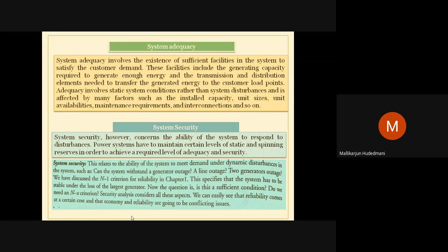That ensures the state of health of the system for upcoming contingent changes. So that kind of measure, Nx criterion based measures, need to be taken as a loop, always keeping alert. If this component fails, or certain components together fail, what is the impact of that failure due to internal failure, external failure, or its own aging effect, whatever it is, the remaining system left is in danger. Is it secured? Is it going to meet the requirement of the power system or not? What are the alternatives to meet that loss should be studied. So that quantifies the reliability, because we define reliability as the ability to be in service for the expected state.